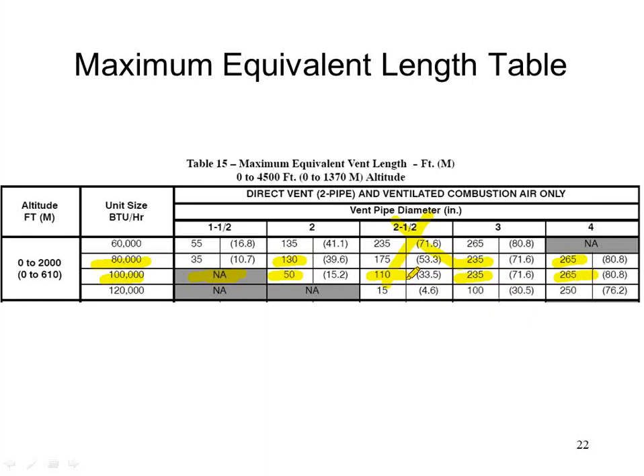Bronson is asking if 2-pipe is not allowed for operational or efficiency reasons. Operational reasons. If you read the installation manual, you're specifically prohibited from doing it. It's not saying that you're going to have lower efficiency. It's prohibiting it. And in general, I don't know that taking outside air would lower your efficiency anyway. You'd actually have colder air, which means colder combustion air, which means you would hit the condensing mode sooner, and you very well may be able to extract more BTUs. So I'm not sure there's any argument there. But it's for operational reasons.